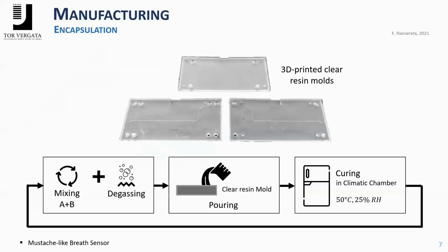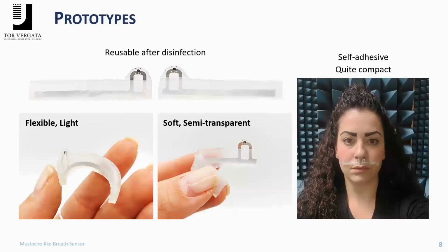The device is fabricated, as was shown before in the other presentation, by producing a 3D printed resin mold. Then we put in the materials; both Silbione and Ecoflex are two-component materials, so we have to mix, degas, and pour, and then you put it in an oven for a few minutes in order to make it more consistent. The device is overall soft and can be attached gently on the skin. You can remove, wash, and reuse it many times. So it's single use for the patient, but a user can use it many times.